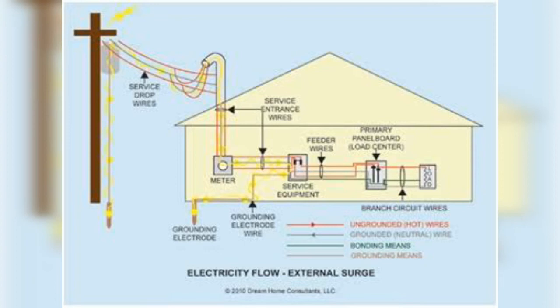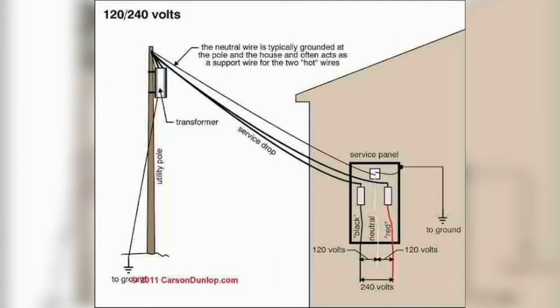In the case of portable appliances, the grounding path in most countries is continuous from the pin in the plug through the flex, so the metal body of the appliance is joined to the main grounding terminal. The grounding electrode conductor, GEC, runs outside the premises to the ground electrode embedded in the soil.